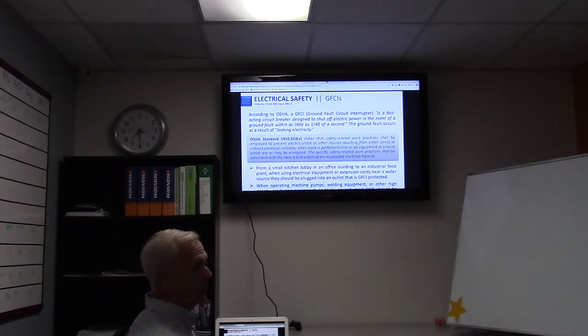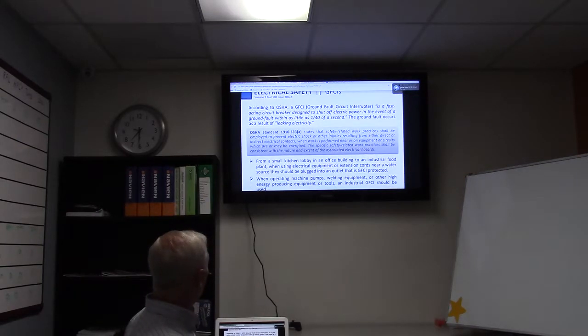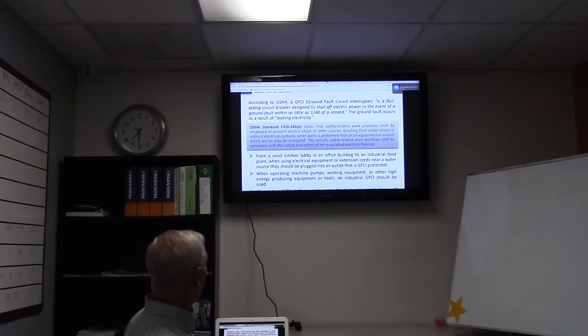So sometimes if that pops, you'll be at another outlet and you plug something in and it won't work, right? That's because it's attached to a GFCI. So then you gotta go searching for a GFCI, because it won't go to the breaker. This is prior to the breaker. The GFCI goes directly to the breaker, however, it's attached to other outlets. So the breaker is not going to pop necessarily because the GFCI does. All you have to do a lot of times is just reset the GFCI and then you're going to have electrical power.